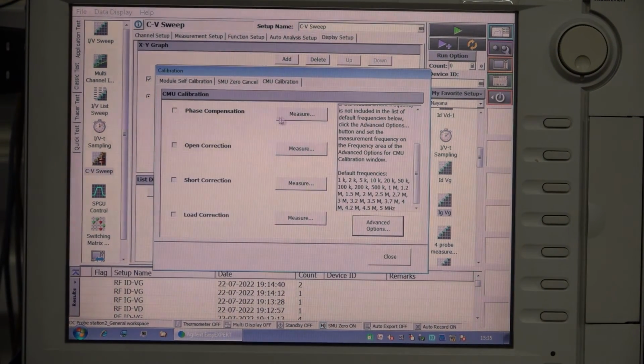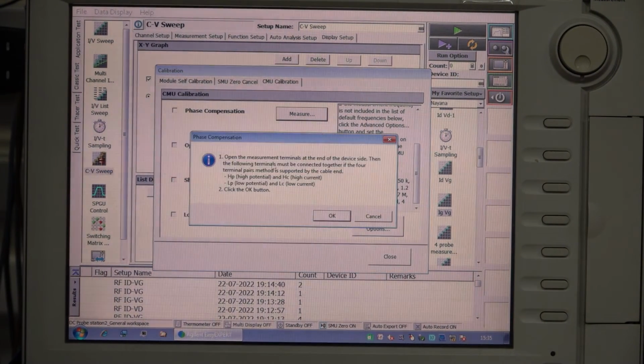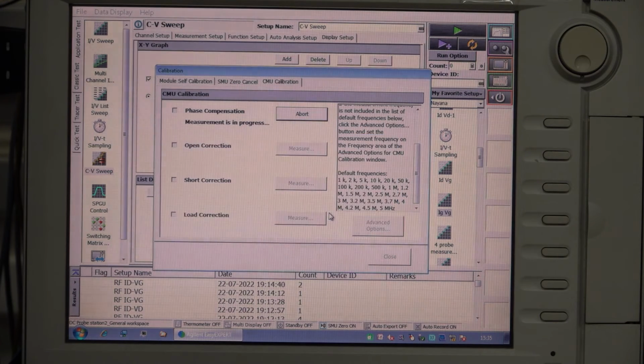First is phase compensation. This says that high potential to high current has to be shorted, low potential to low current has to be shorted, and the device under test has to be removed. We have done that, so we'll click OK. Once the calibration is done, there is a tick mark here. This indicates that the calibration is done and the values are stored in the buffer.